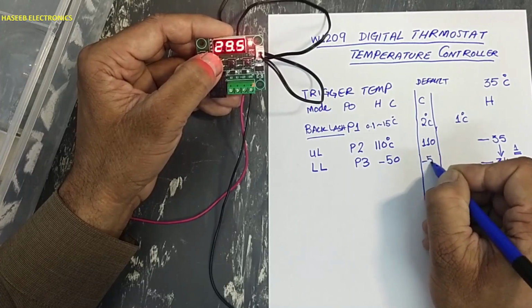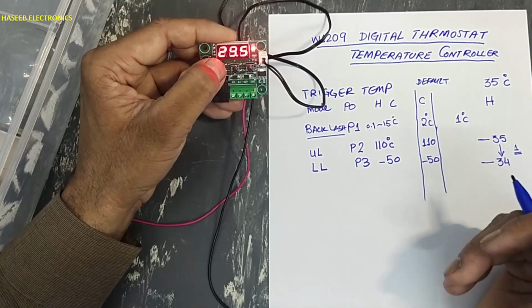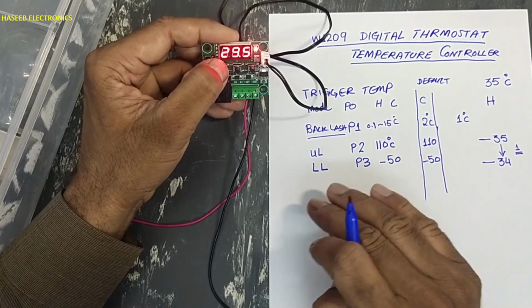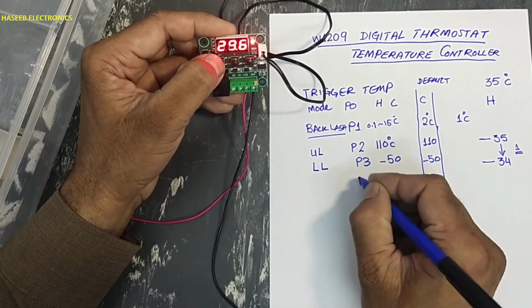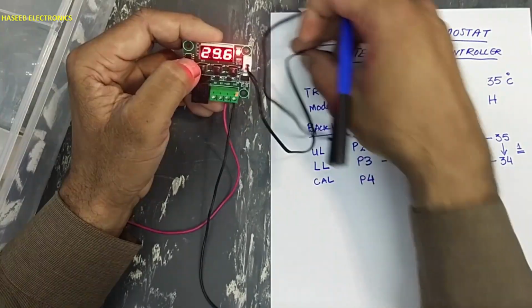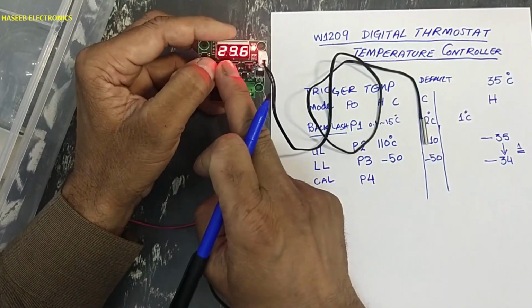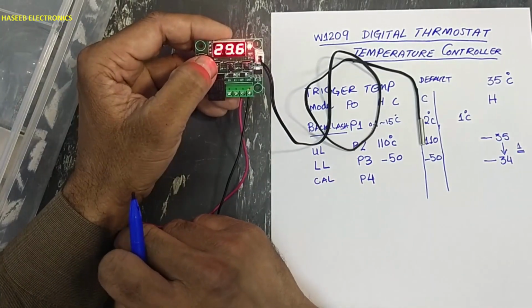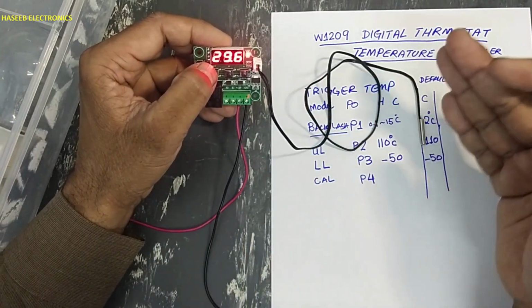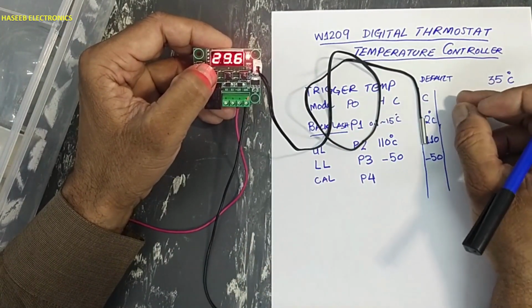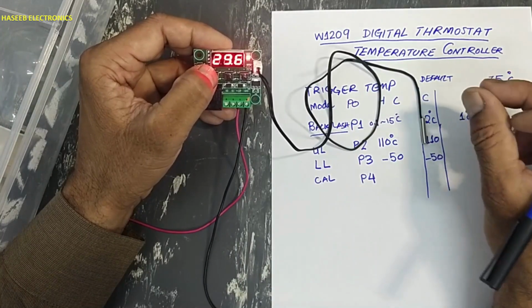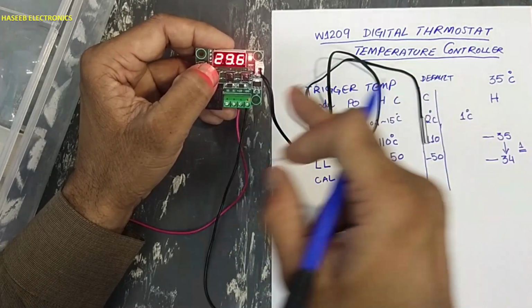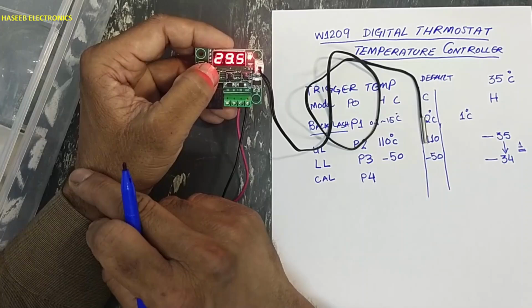We can set to any temperature which we want. That is borderline. Then P4. P4 is calibration. Let's suppose here it is showing 29.6 degrees. We have an external thermometer. That thermometer is reading 30 degrees. So there is 0.4 difference.